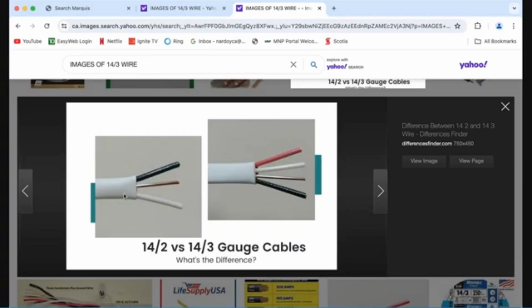This one on the left, we have a black conductor and a white conductor - the ground we do not count. This is 14-2 conductors. The image on the right is American wire gauge 14, 3 conductors: red, black, and white. That is what we are bringing from the electrical panel to that receptacle. We are making the red wire go to one receptacle and the black to the other. Does that clear things up for us?